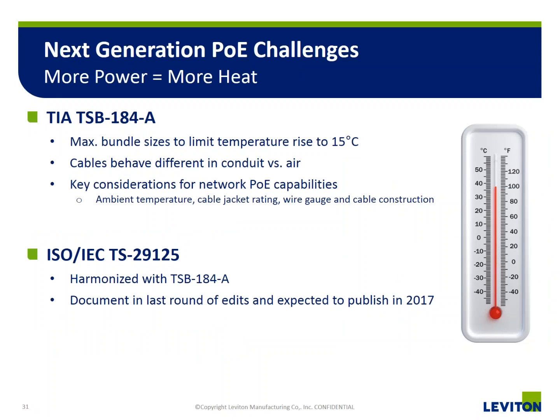One caution, however: with power comes heat. The standards bodies, both TIA and ISO, and a lot of the cabling manufacturers have been spending a lot of time investigating what happens when you start to run power over the cabling system, and how that impacts safety and design. What we have found is that the more you bundle the cables together, the more the cable at the center can heat up.